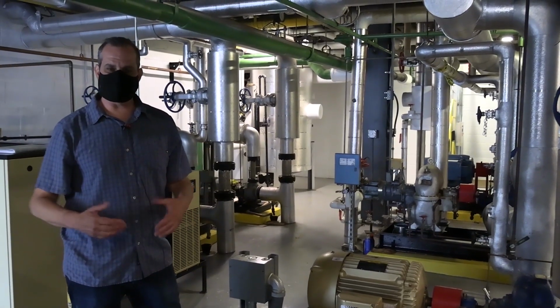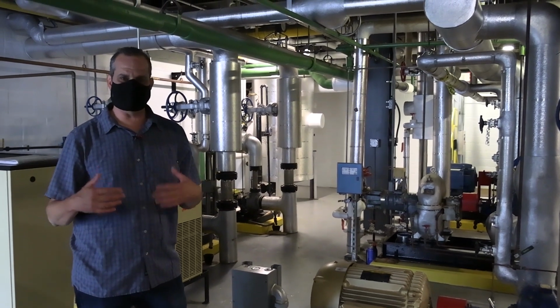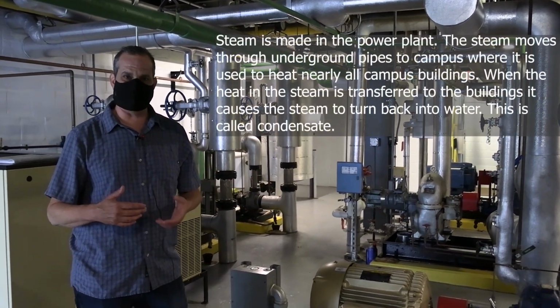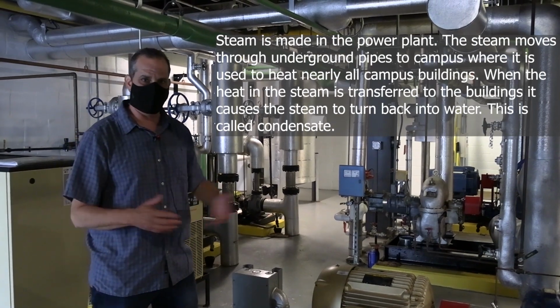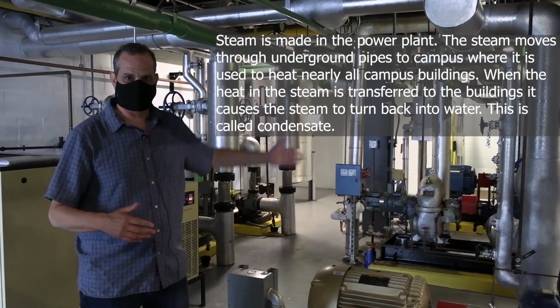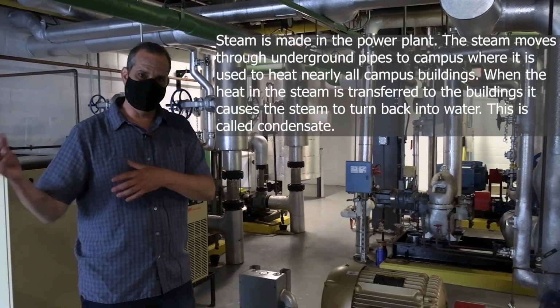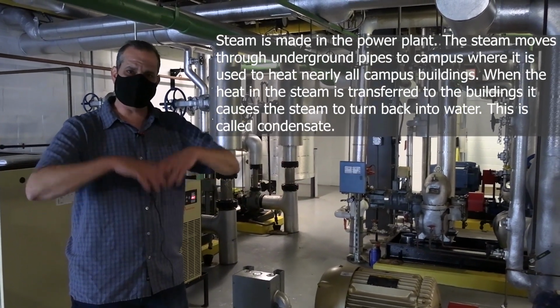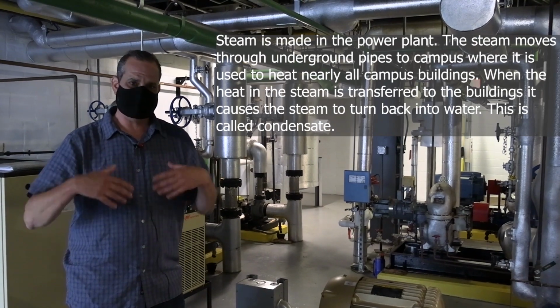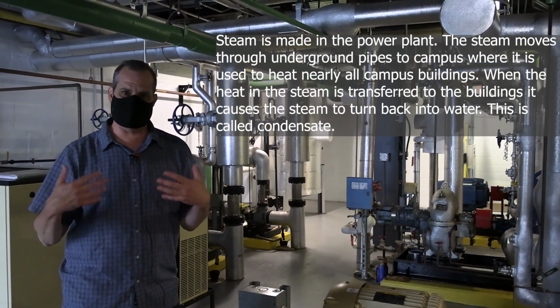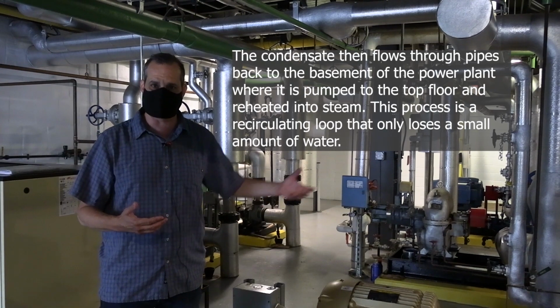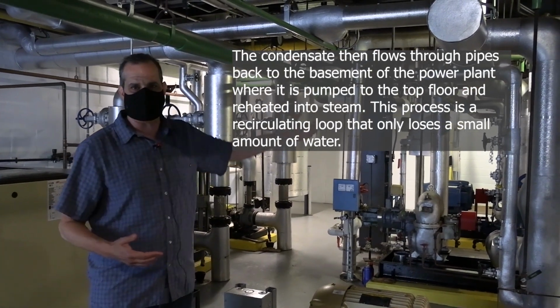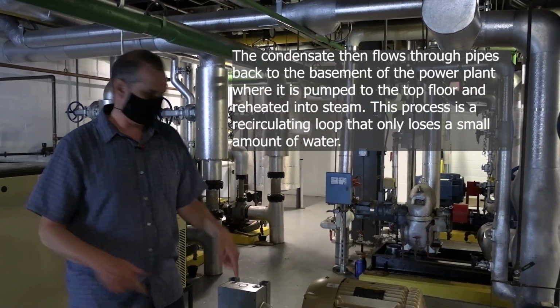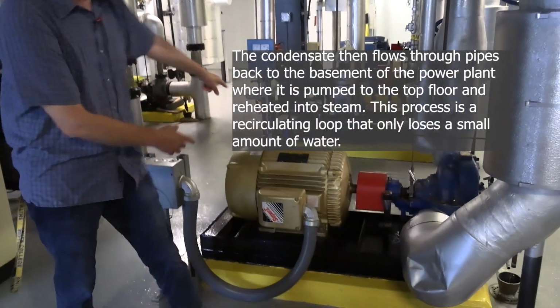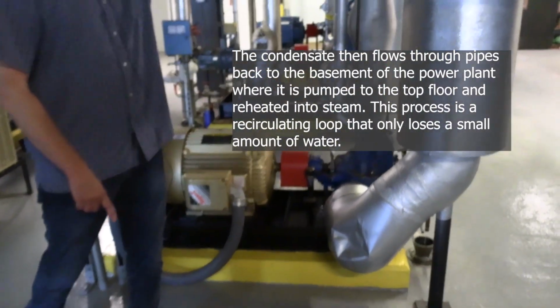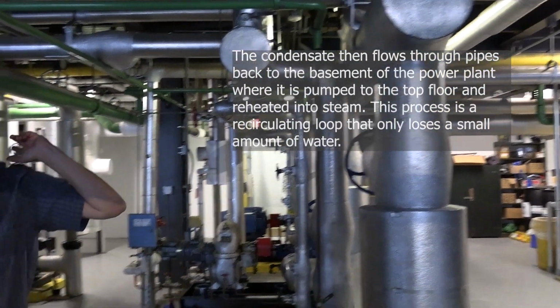As we mentioned before, Smith distributes steam around campus, and that's how we move heat from this building all the way around campus, up to the quad. The pressure of the steam moves it through the pipes. When it gives up its heat and loses its energy, it turns back to water, what we call condensate. The condensate flows by gravity all the way back down the hill to this building, into the basement. These are pumps, which pump the water out of the basement and back upstairs where we make steam again.